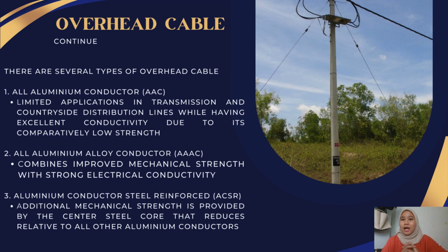There are several types of overhead cable. First is all aluminum conductor, AAC, which has limited applications in transmission and countryside distribution lines, having excellent conductivity but comparatively low strength. Second, we have all aluminium alloy conductor, AAAC, which combines improved mechanical strength with strong electrical conductivity. And last, we have aluminium conductor steel reinforced, ACSR, where additional mechanical strength is provided by the center steel core, which reduces the conductivity relative to all other aluminium conductors.